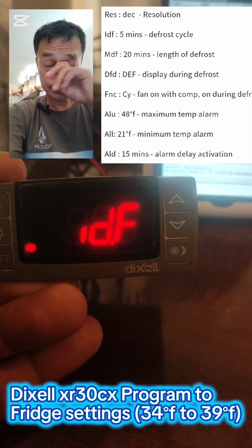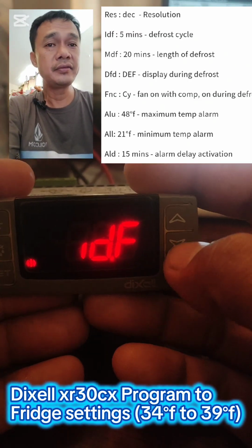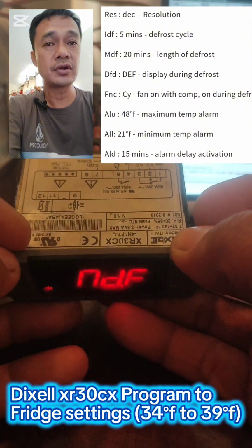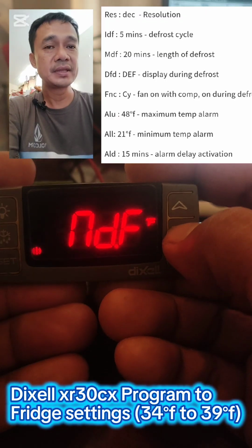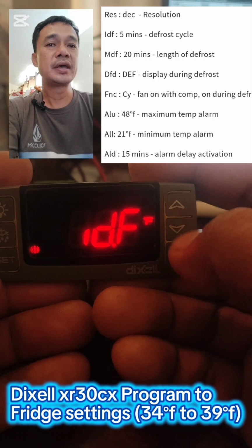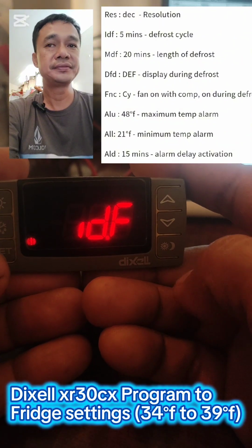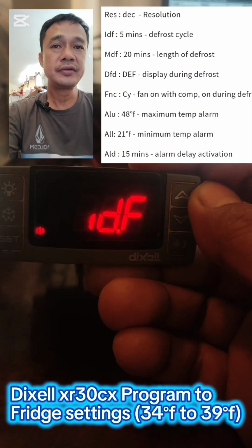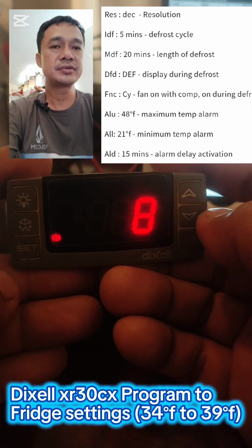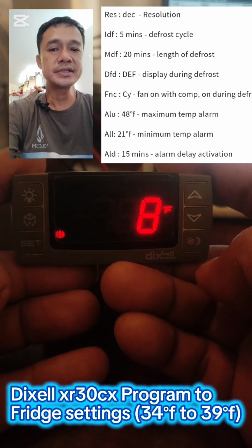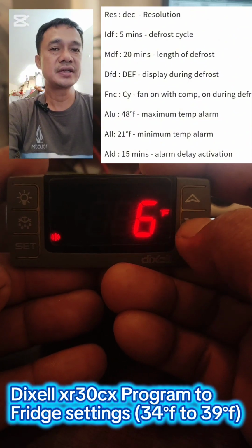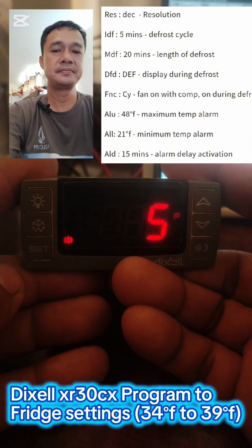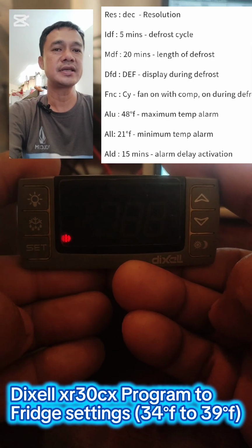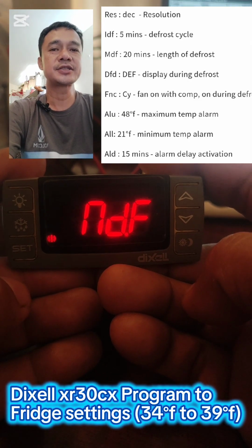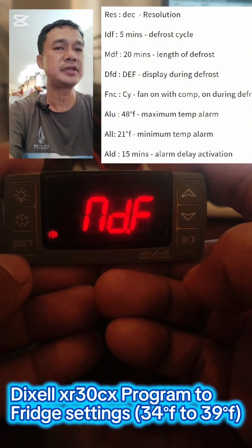And now let's go here. This control has a code for the defrost, although there is no output relay for the defrost heater. So we're going to set that. And let's start with the IDF. IDF stands for defrost cycle, and it's set to 8 hours. But for a fridge, I usually set it to 6 or 5, every 5 hours. So press set to memorize, and let's proceed to MDF here.